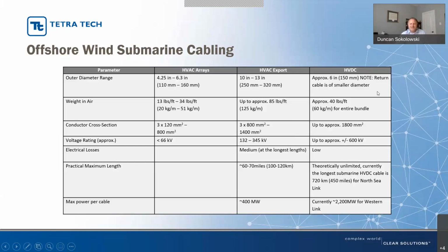If you look at HVDC, the cables are smaller - about 6 inch diameter for the cable. They are a little lighter, cross sections bigger, but it's a single cable for the conductor. Voltage level is higher, the losses are lower, so they can transmit power over a much greater distance. At the moment, the longest submarine HVDC cable is about 450 miles - that's the North Sea link in Europe. They can also transmit a lot more power, about 2,200 megawatts for DC cables at the moment.